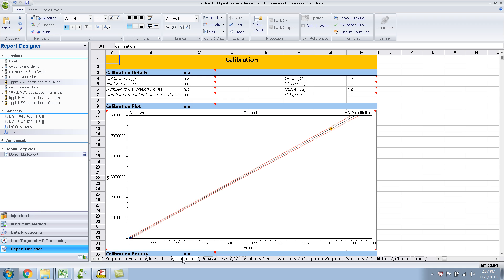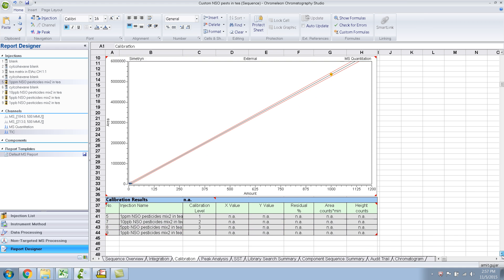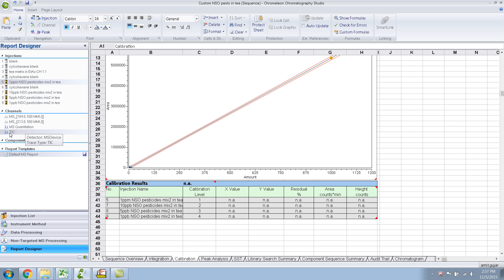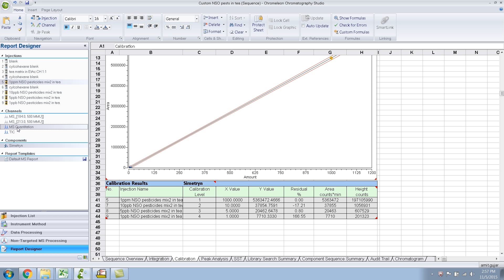The calibration report over here will give you the calibration plot, obviously. And where does it say X? That's because the calibration itself is done on the MS quantitation channel, and what I've clicked is the TIC or the total ion chromatogram. So let me click on the MS quant channel, and you should see the proper values for the X axis, Y axis, and areas and stuff like that.